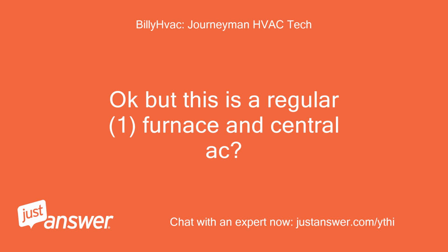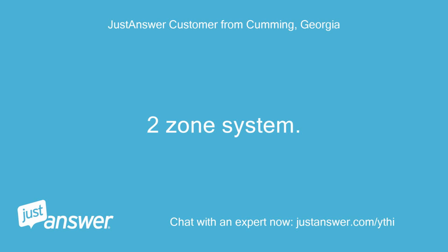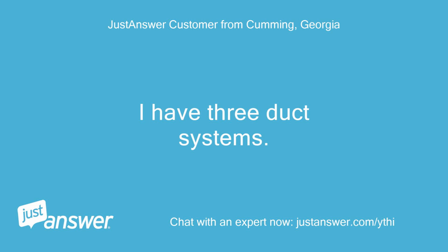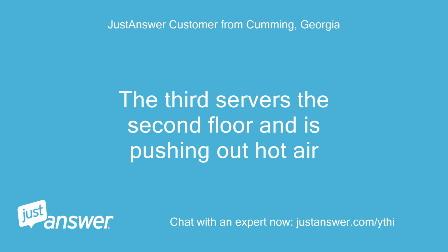Okay, but this is a regular, one furnace and central AC? With one zone control panel? 2-zone system. Downstairs is fine. Upstairs is a sauna. 1 furnace, 1 AC. I have 3 duct systems. 2 have the dampers daisy chained, the third is independent. The third serves the second floor and is pushing out hot air.